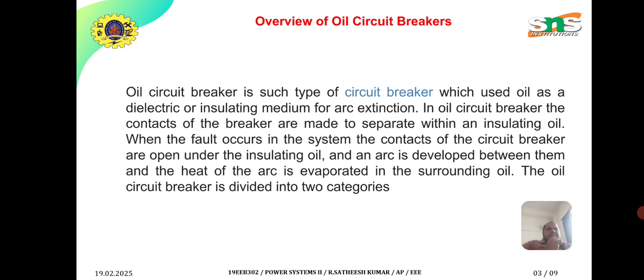An oil circuit breaker is a type of circuit breaker which uses oil as a dielectric or insulating medium for arc extinction. In an oil circuit breaker, the contacts of the breaker are made to separate within an insulating oil. When a fault occurs in the system, the contacts of the circuit breaker open under the insulating oil, and an arc is developed between them. The heat of the arc evaporates the surrounding oil.